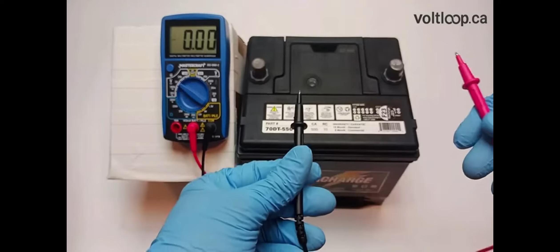Symptoms are identified to help you determine what to test to find the fault. There are only three faults that can occur in an electrical circuit: an open, a short, or a change in resistance, which in most cases goes up.